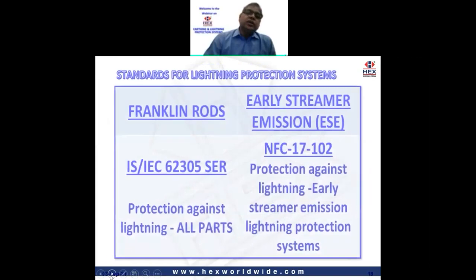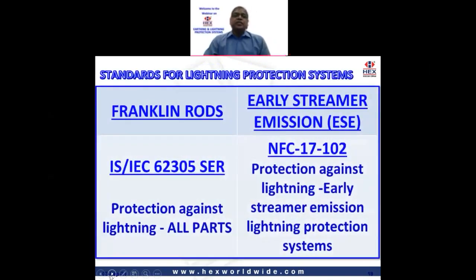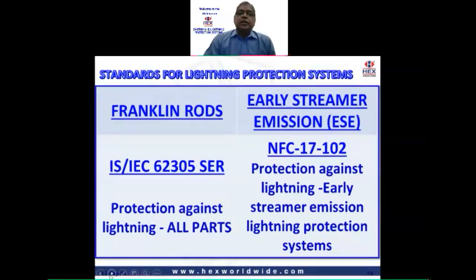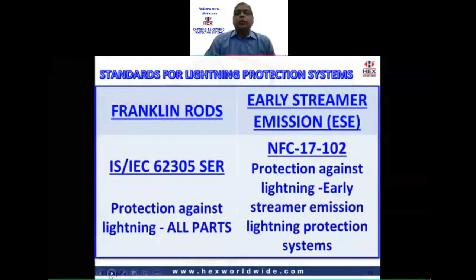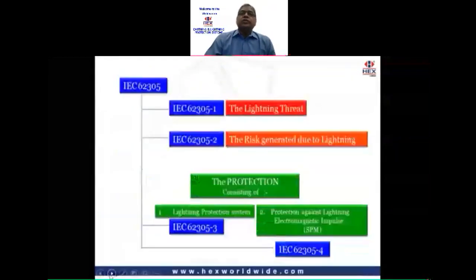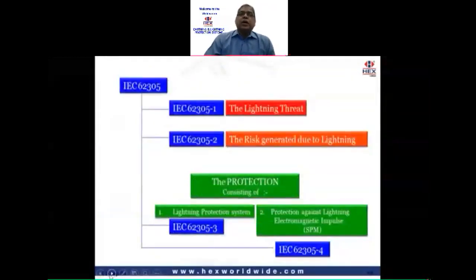Both these types of lightning arresters have their own standards. The Franklin rods are governed by IEC 62305, which is a series of four parts. And NFC is for the early streamer emission devices. Talking about IEC 62305, the four parts: it talks about the threat of lightning, part one. The threat is to the source of the damage, the type of damage, and the type of loss that can occur due to the lightning threat.